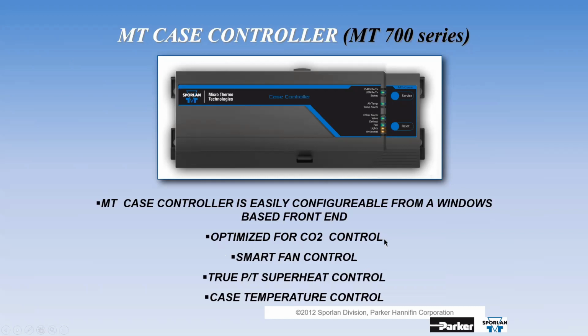It was originally designed for CO2 8 years ago, but we quickly made it so that it can control any of the current refrigerants that are out there, not just CO2. It does smart fan control, a true pressure temperature superheat control, and also case temperature control. There's 4 modalities to this. We can do superheat control with temperature backup. We can do temperature with superheat backup, or we could do pure superheat control or pure temperature control.